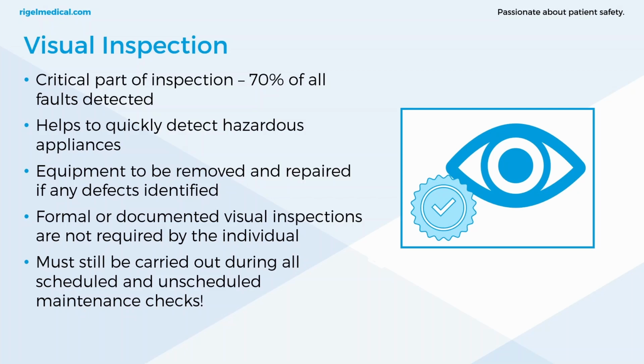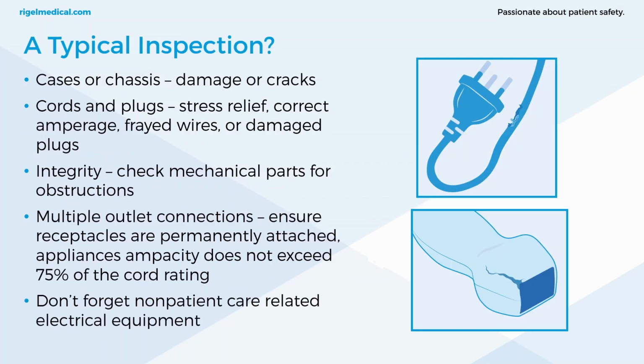Now on our 2 Plus, so that's our automatic safety analyzer, we do have an option to add a visual test at the beginning of the test sequence, and then you have to manually check, pass or fail through those series of checks, which can be a useful prompt for any new users in the workshop. So what does a typical inspection include? So cases or chassis, looking for damage, looking for cracks or damaged plugs. These are all just sort of common sense faults that as experienced biomeds you'll know what to look out for straight away. However, this list could be useful to have somewhere in the facility.